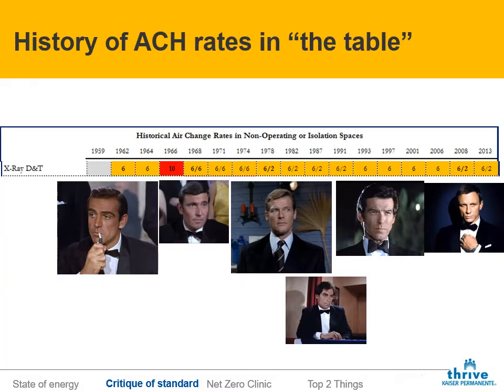So let me wrap up on standard 170. This is a chart that I've shown in my presentations before of the standard air change rate in X-ray rooms plotted against the actor who played James Bond. I always point out that Sean Connery is smoking a cigarette, which would have been fine, in an X-ray room in 1962. But basically, you can see we've always used 6 air changes. We use 6 air changes because we've always used 6 air changes.